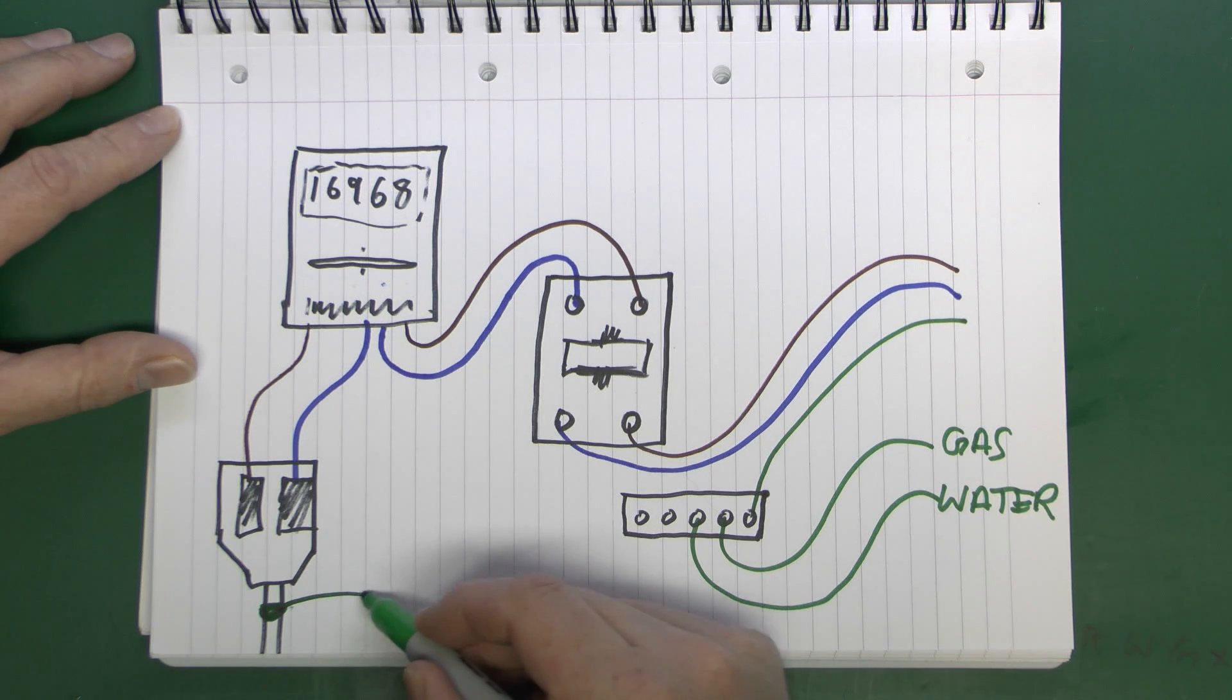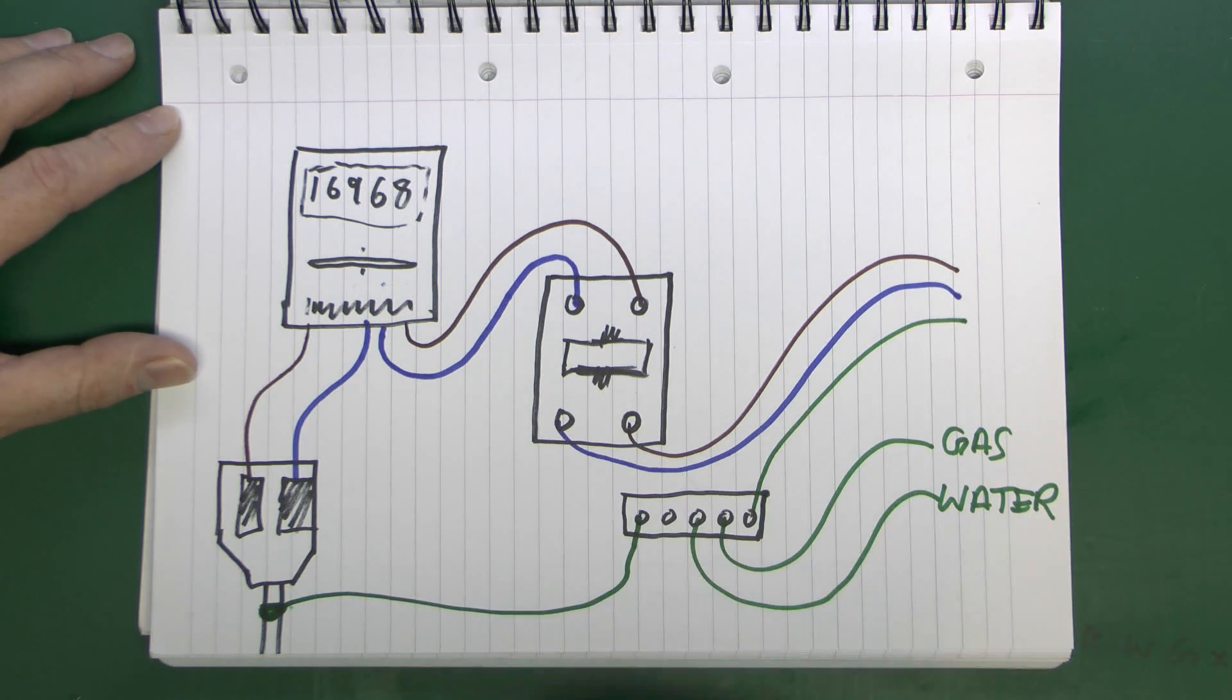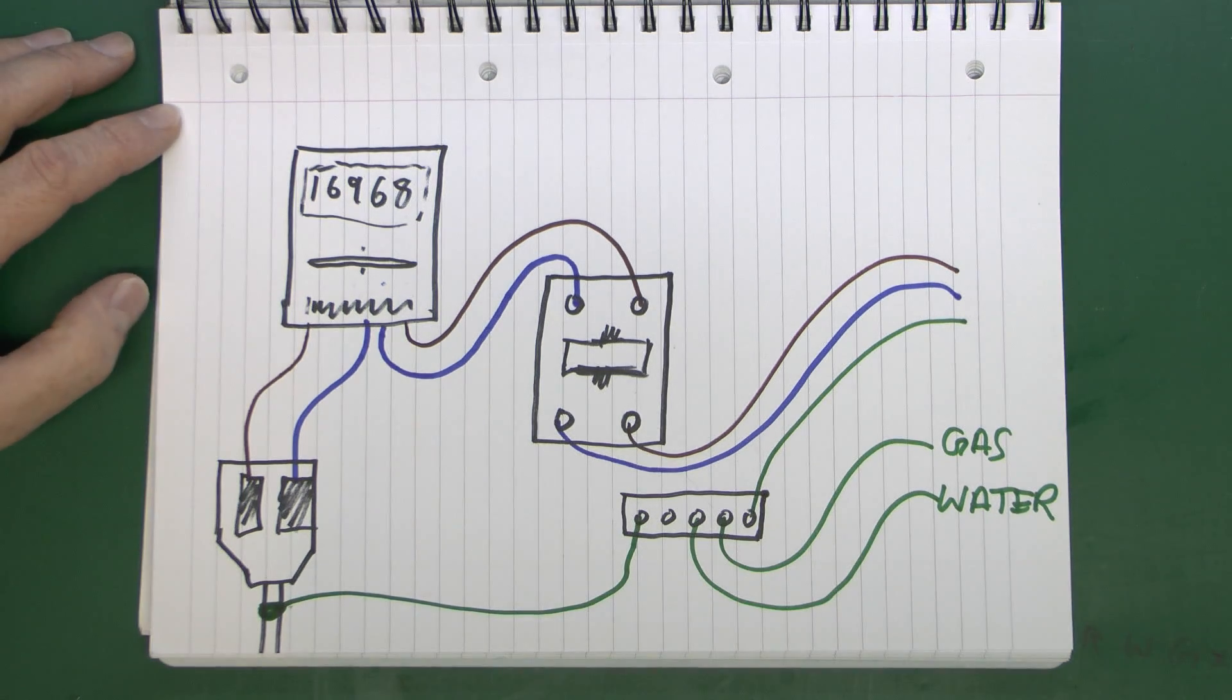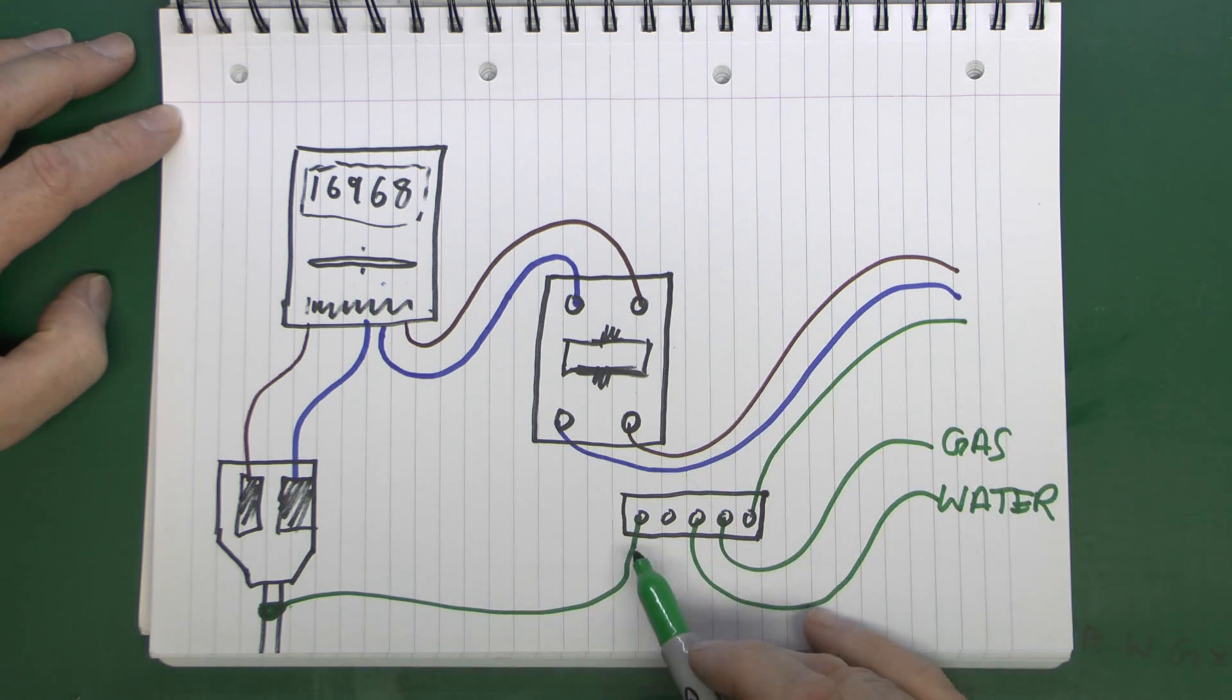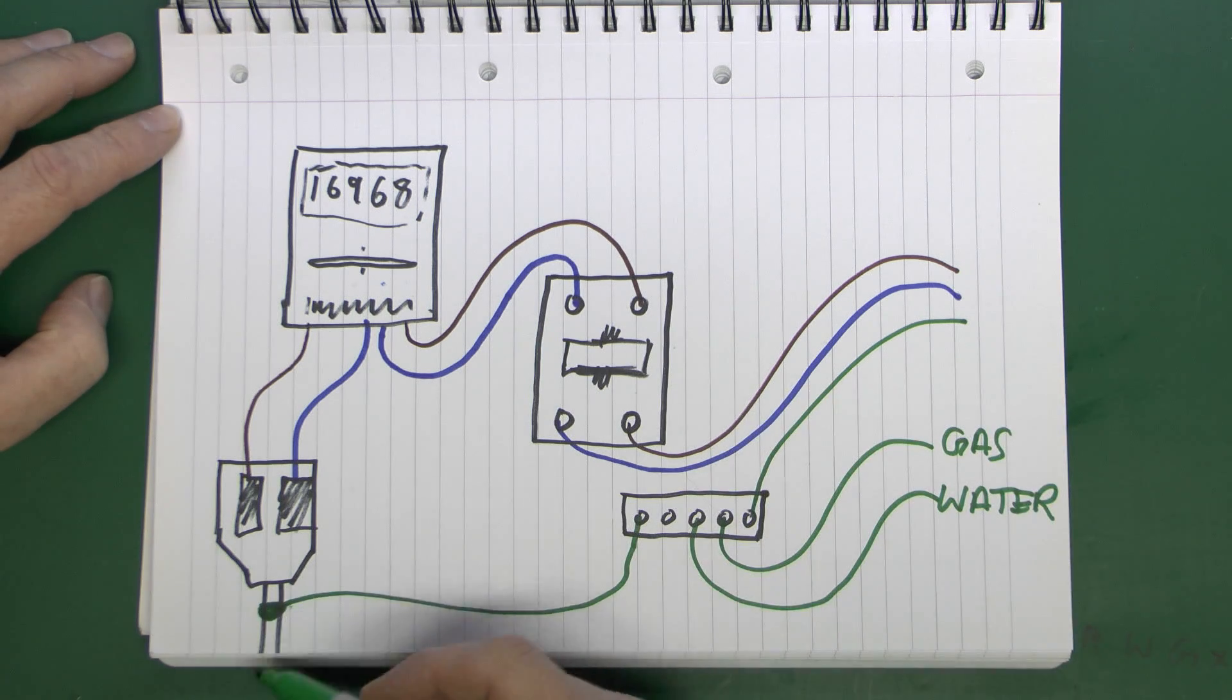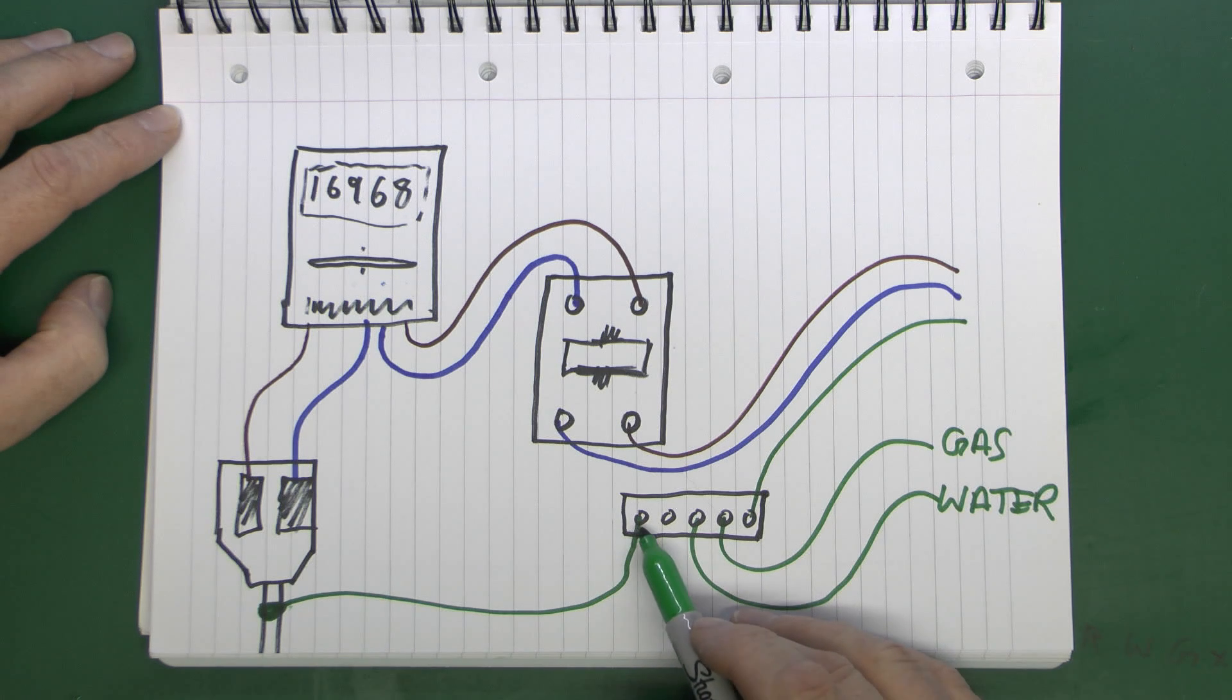That will come across and go into the earthing bar like that. Now in order to test this, what we need to do is to only test this piece here and the external earth connection, so we need to actually disconnect this from the actual earth bar here.